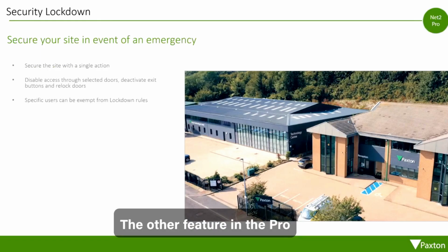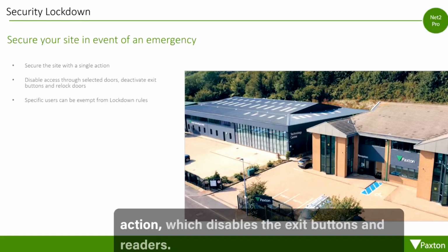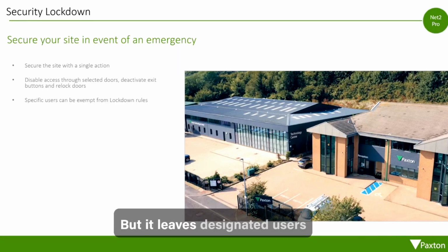The other feature in the Pro software which I wanted to highlight is security lockdown. The lockdown enables you to secure your site with a single action, which disables the exit buttons and readers, but it leaves designated users immune from the lockdown. People such as security staff, for example: you might want them to still be able to move around the building so they can deal with the threat.